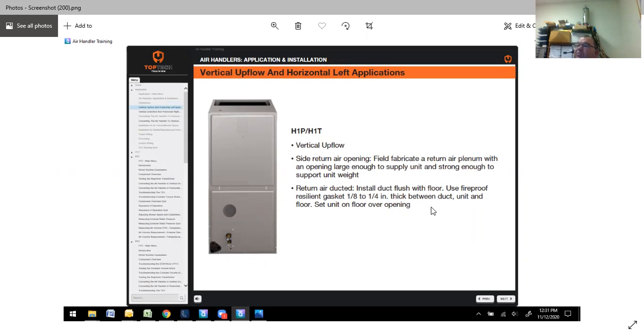The vertical upflow, which is going to fall into the RH1P, RH1T. Side return air opening: you must field fabricate a return air plenum with a large enough opening to ensure proper airflow. And also a big one is strong enough to support the unit's weight. I came across one a long time ago, and it had actually buckled the box. It was still all hooked up, so that was a real treat to try to support the unit, take out the old broken box, put a new constructed box in there, and put it all back together again without having to unhook every single thing.